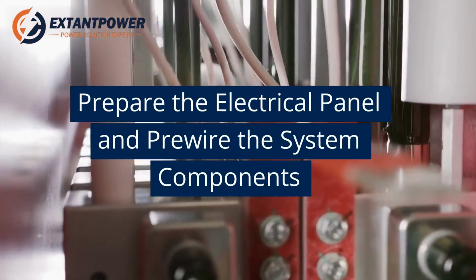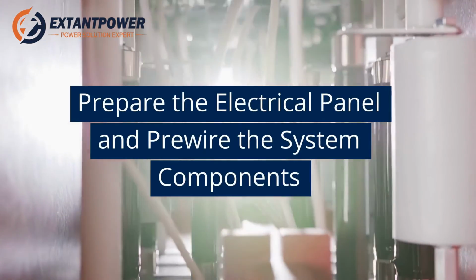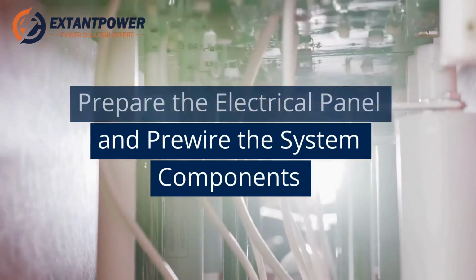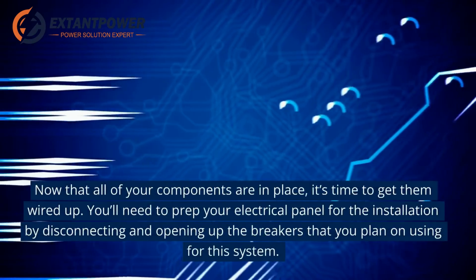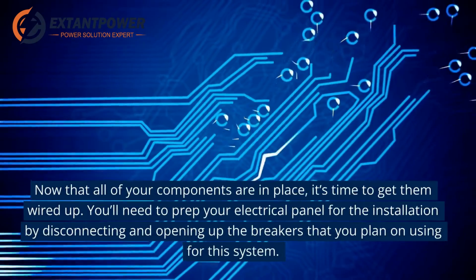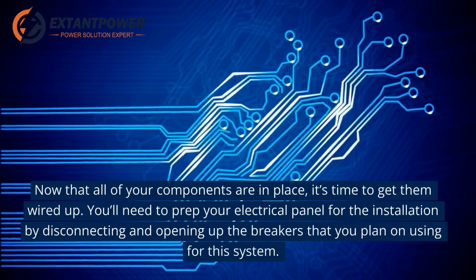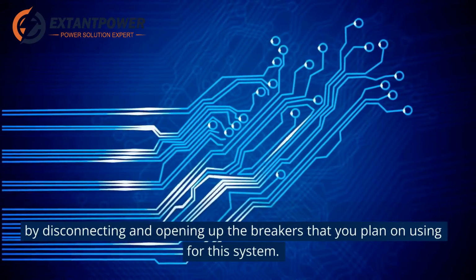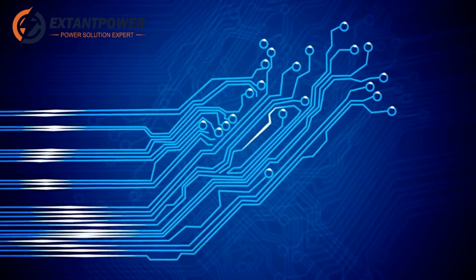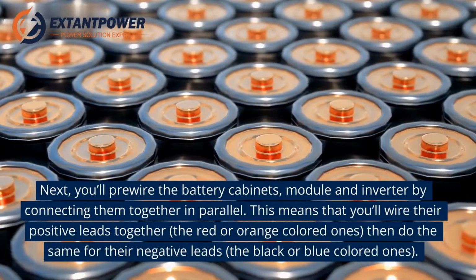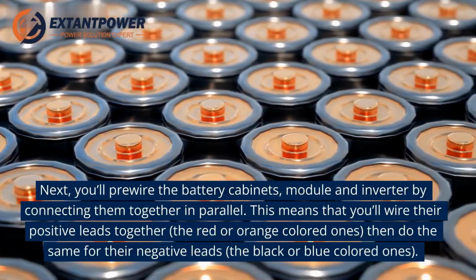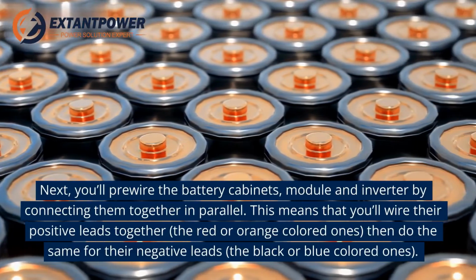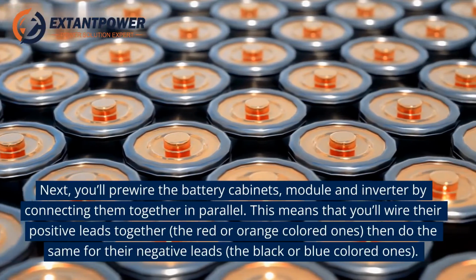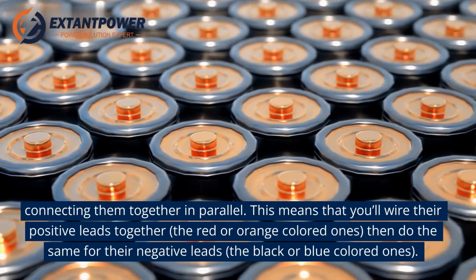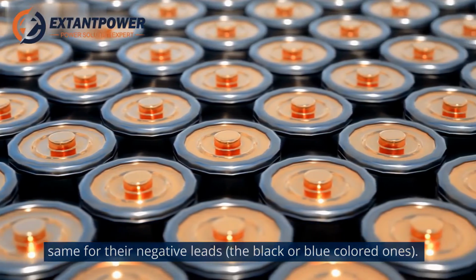Prepare the electrical panel and pre-wire the system components. Now that all of your components are in place, it's time to get them wired up. You'll need to prep your electrical panel for the installation by disconnecting and opening up the breakers that you plan on using for this system. Next, you'll pre-wire the battery cabinets, module and inverter by connecting them together in parallel. This means that you'll wire their positive leads together, the red or orange colored ones, then do the same for their negative leads, the black or blue colored ones.